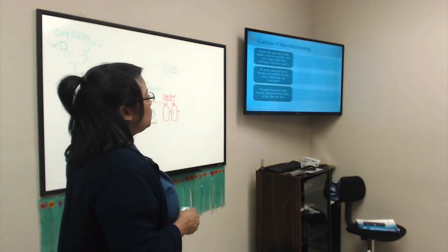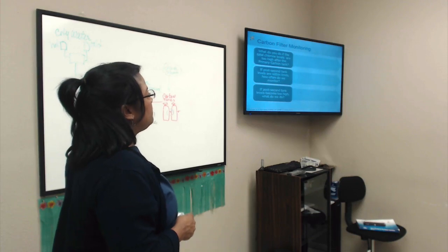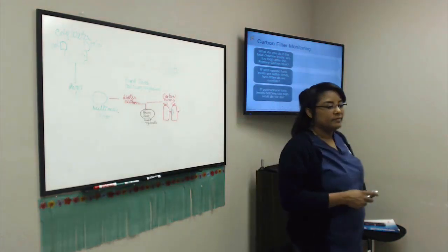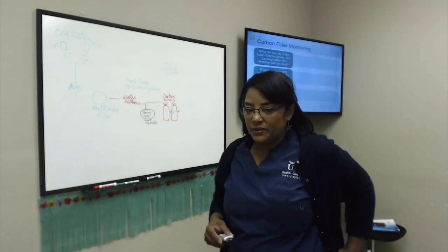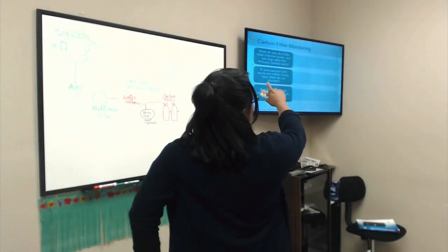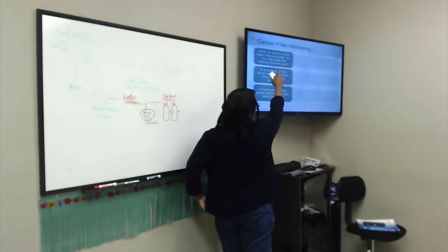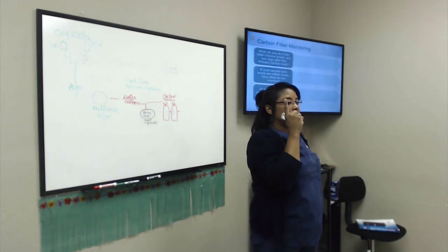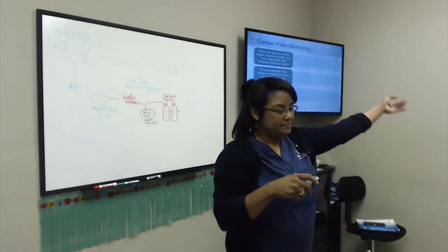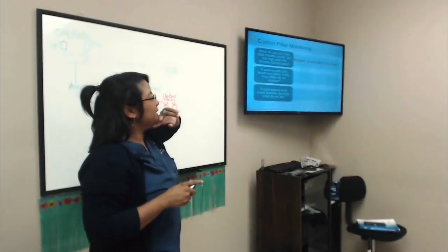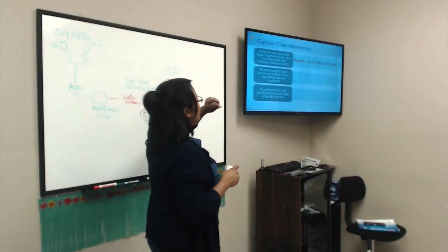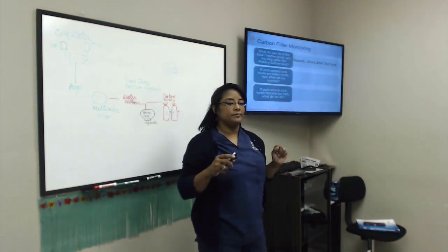So again, what do you do if the chlorine levels are too high after the primary carbon tank? Try not to look at your paper, based on what we discussed. What do we do if the chlorine levels are too high after the primary carbon tank? The first test. Check the second. Repeat, check after the second tank. If the post-tank levels are within limits, how often do we monitor? Every 30 minutes.